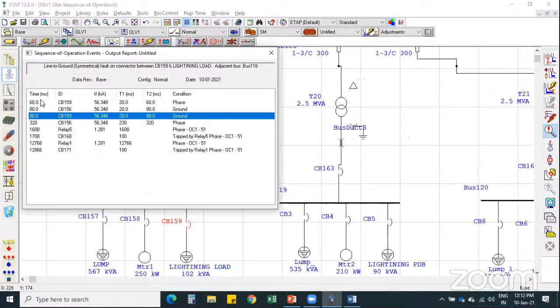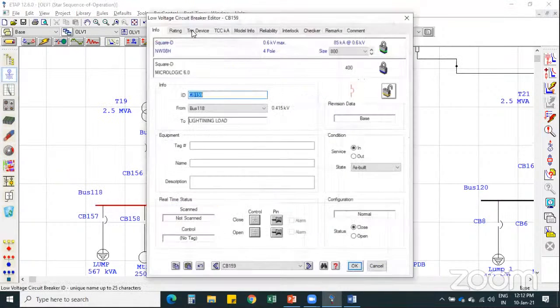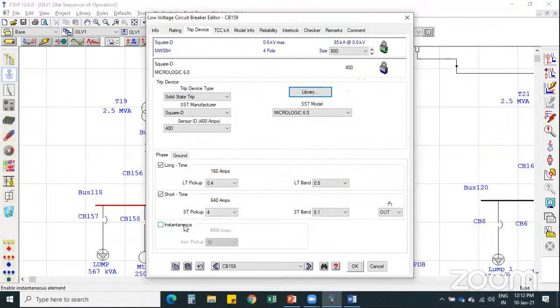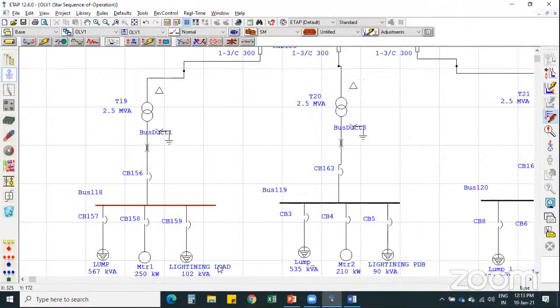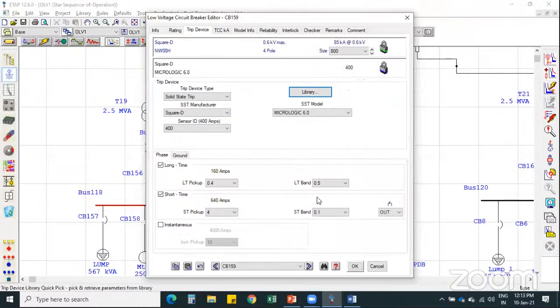So for this, there are 2 provisions we need to adopt. The first one is that we can turn off this protection. It's the extreme downstream network, so we can turn off this protection, and simply with the help of this, the protection will be achieved with the short circuit condition also. So this is an overlapping protection. If we want to add it, we can. But normally what we suggest is to disable this protection, because many times malfunctioning of this protection is observed at the practical stage. So what we recommend is to disable the instantaneous protection for this LVCB trip unit.